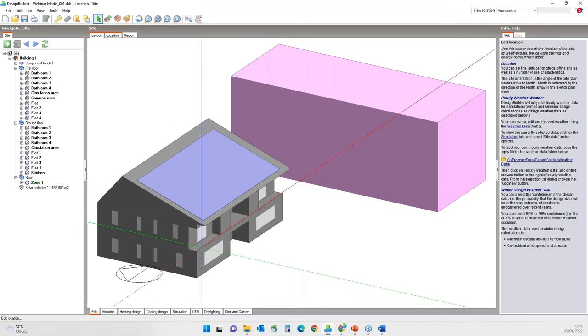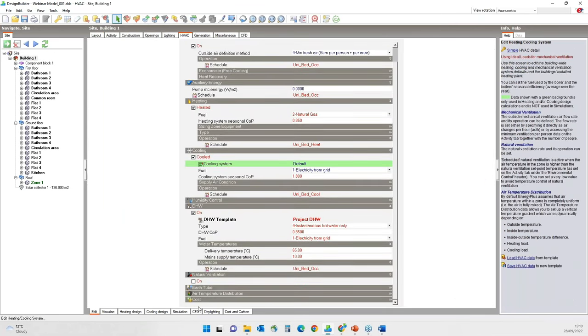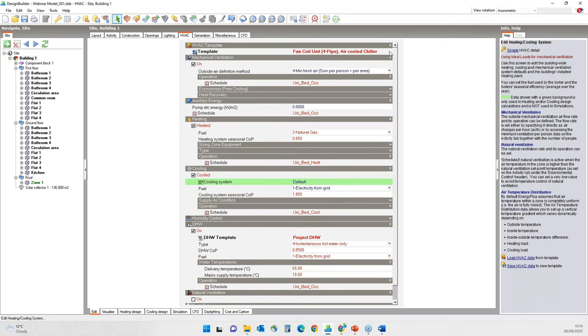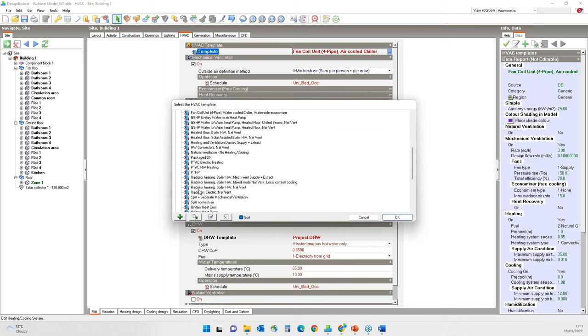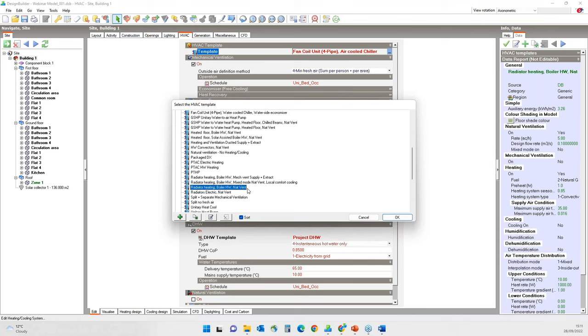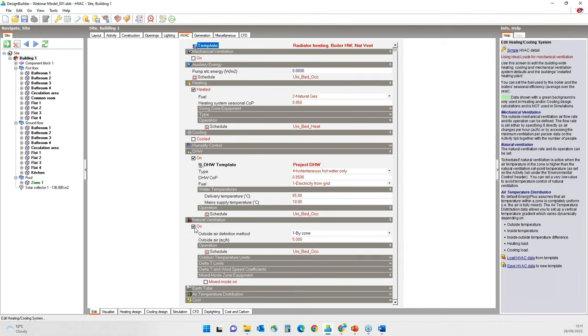First, you must ensure that the site location and the weather file are correct — I will leave it to London Gatwick Airport. Now going into the HVAC tab: the option here allows you to include natural ventilation in your model. You can consider this checkbox like a main on-off switch for natural ventilation. If you can't see a natural ventilation input you expect, check that natural ventilation is switched on here. I will select the radiator heating with boiler, hot water and natural ventilation system template. Once loaded, you can see that mechanical ventilation and cooling have been switched off, and natural ventilation has been switched on.